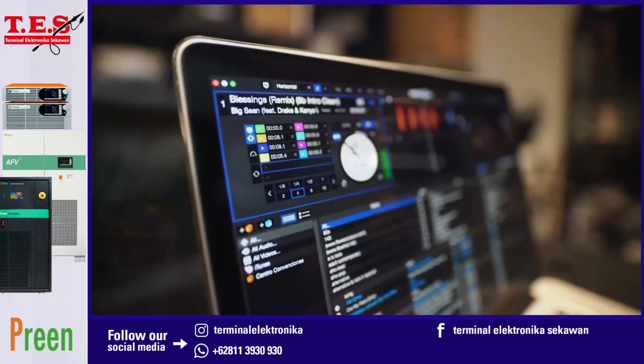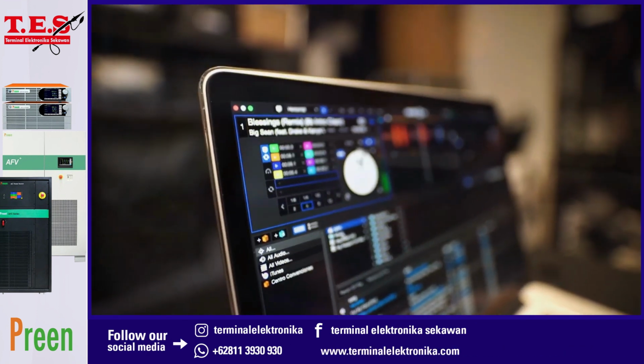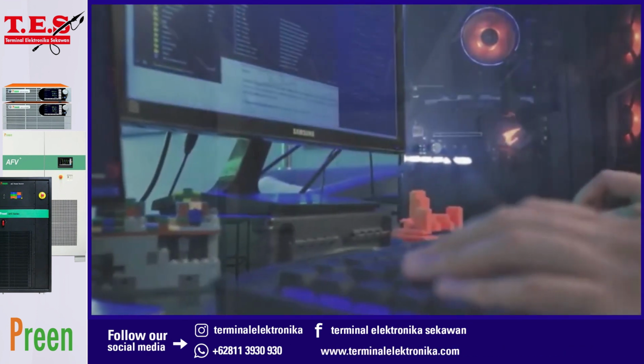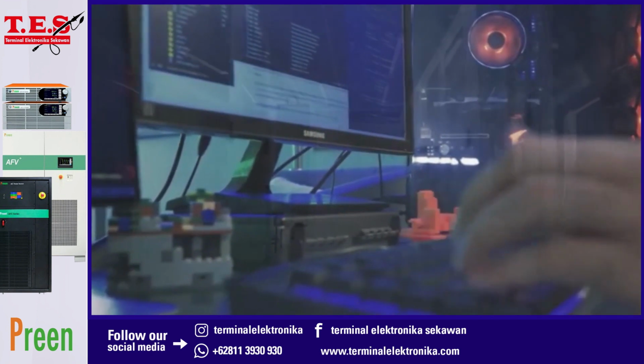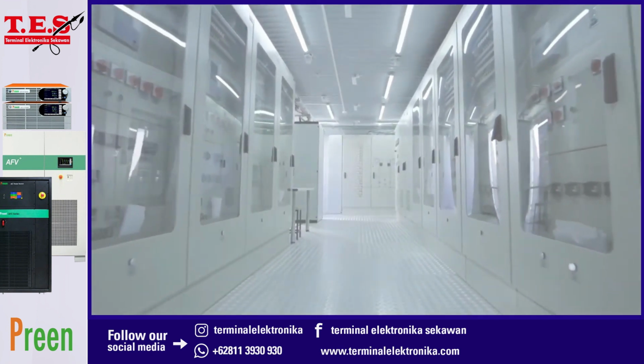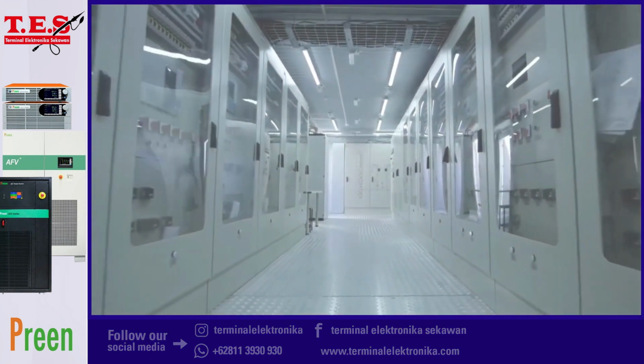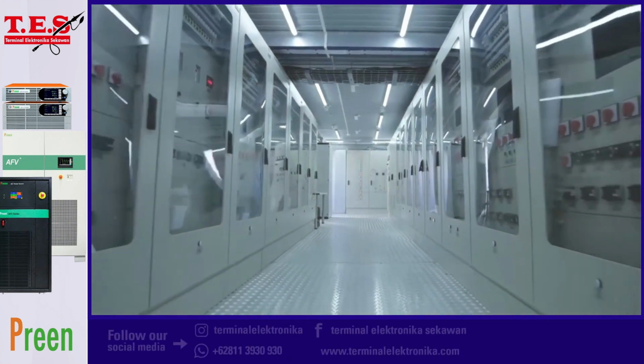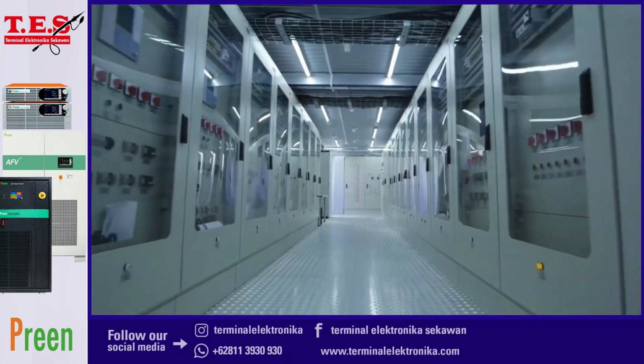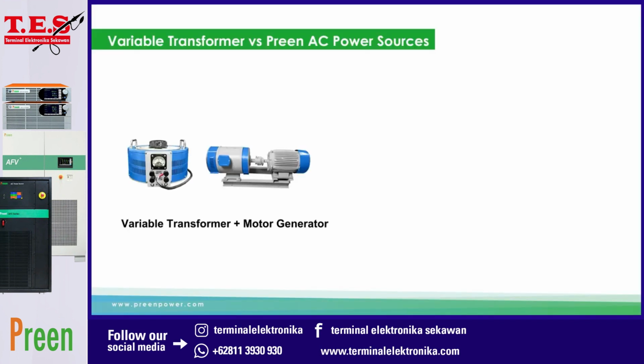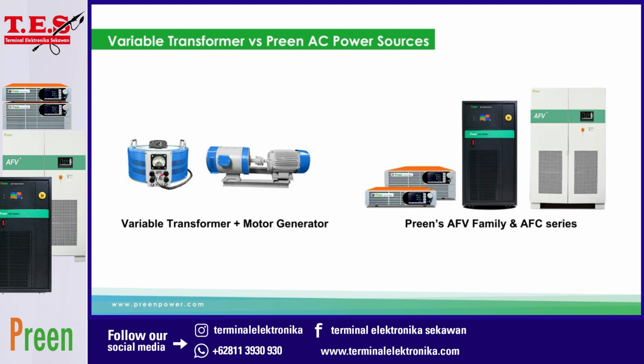With the advent of globalization, electronics need to meet the power requirement of different countries. Especially during the R&D and production stages, voltage and frequency variation tests are essential. There are two ways to conduct the voltage and frequency variation test. One is using a variable transformer along with a motor generator, and another one is using frequency converter or programmable AC sources, which provides remote control capability.